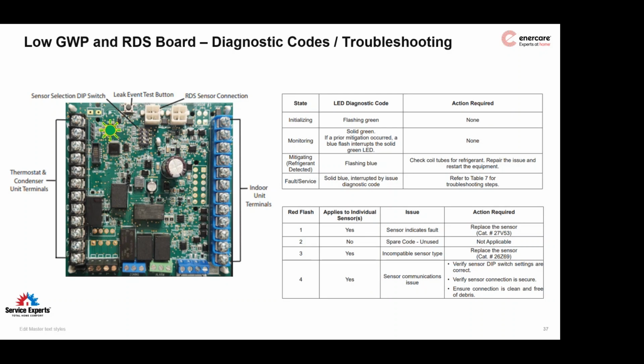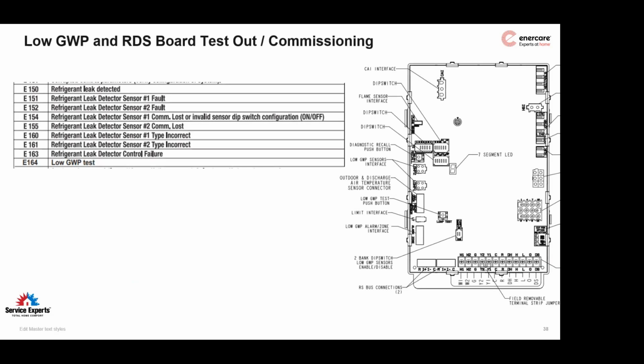Terry? I know this is also on the service side, but is there a life expectancy of these sensors, considering they're supposed to be sensing your gas vapor? Your guess is as good as mine. It's like they say with all the gas detectors that they have out there, you want to replace them every 10 years or something. So my thinking is, if a guy goes back in later on to replace one of these units, do we have to replace the sensor? In my opinion, from a service guy's perspective, I would probably change the sensor, but yeah.